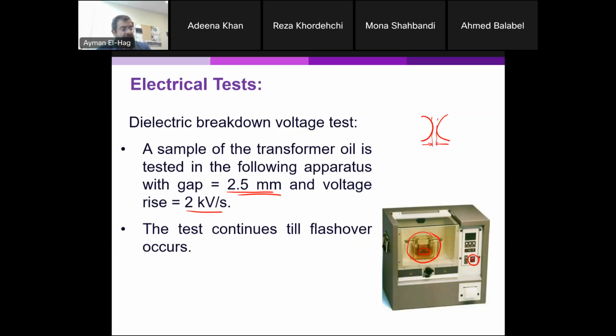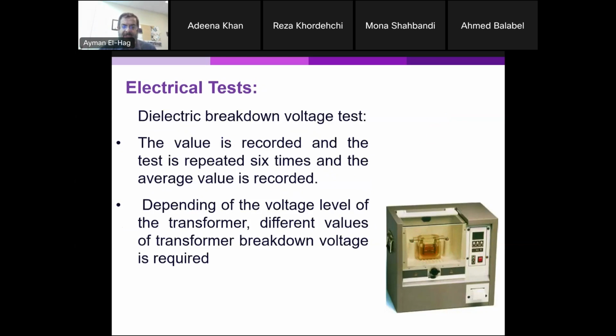Now, when the flashover happens, and as usual, this is an oil. It's a mineral oil. It's a hydrocarbon. Some carbon will be released. Okay. Now, one test is not enough to get a value of the breakdown strength. So the test is actually done 6 times. So repeat the test 6 times, and we take the average value.